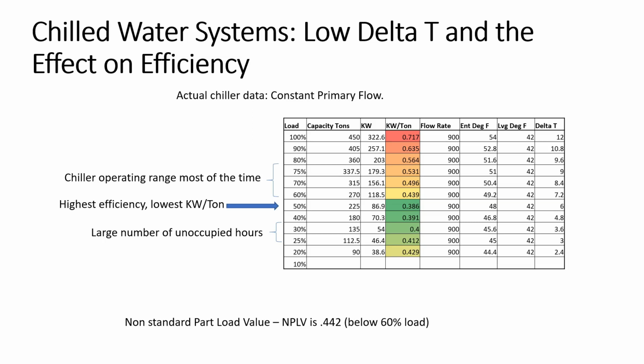So in this case, they're operating on both sides of the most efficient point. And really, if they'd have resized the chiller, they probably could have dialed it in to where you get all these hours of run time at its most efficient point. But in this case, they're bracketing above and below. So I guess they took a shot, put in a chiller that they thought would be most efficient based on those hours. It's obviously going to run between 75 and 25%, but that's maybe not the most efficient point.